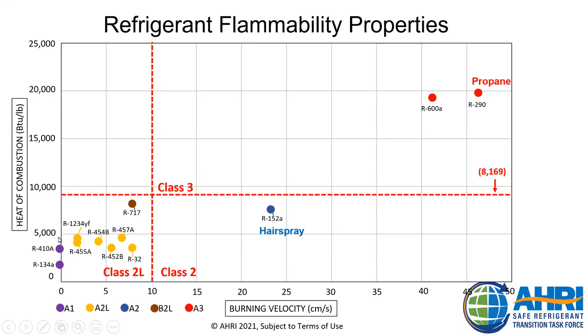Here's the amount of energy it would release. And if I look at all of my A2L refrigerants that are in here, and actually even one that's a B2L, ammonia, they're all in this same box. So you can see they all have a very similar energy release. And again, looking at the burning velocity, or how fast a flame front would move, you can see that these are very similar, not the same as 410A or 134A that's used in a refrigerator, but very similar. So again, looking at the refrigerant flammability properties, the A2Ls are a lot closer to A1 refrigerants.